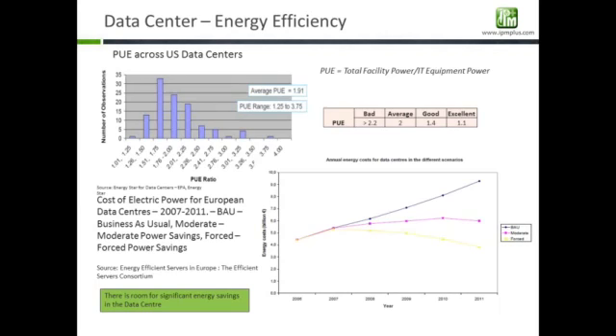The EPA and other agencies have done quite a bit of study across data centers in the US and Europe, and they use a metric called power utilization efficiency, or PUE. A data center has electrical power coming in. Part of the power is used for air conditioning, cooling, lighting, and so on. The rest is used for actually powering the IT equipment, which is the server, network, and storage devices. The ratio of total electricity power to the power consumed by the IT equipment is called the PUE.